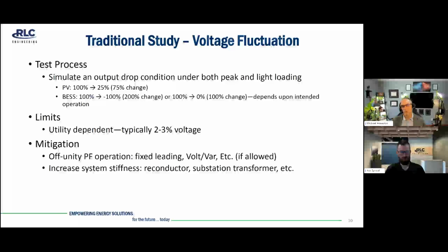And it depends again on what the developer and utility have agreed upon as far as how that device is going to be operating. The limits are utility dependent; 2 to 3% is a common criteria we'll see. And things like off unity power factor can help with these. So fixed leading, volt-var. StatCom is not on this list, but that can also be a mitigation. Increased system stiffness, reconductor, substation transformer, things like that.